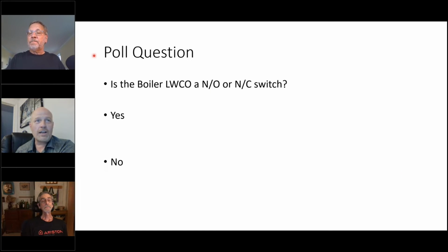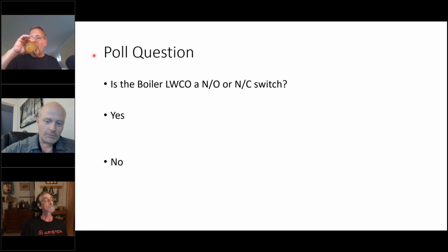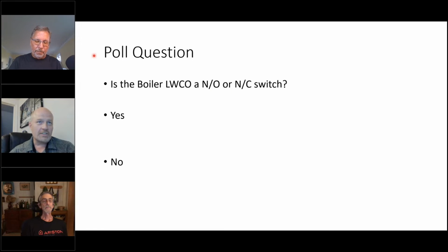So although the low water cutoff should remain closed anytime the boiler's operating, it's actually a normally open switch. The standalone condition of this switch, if you just sit it on your desk, when there's no water touching it, is in the open condition. It does not make the contact, and it's adding water that creates the contact. So although the switch itself generally remains closed for the life of the boiler, the switch's natural standalone position is actually open. So it's a normally open switch that closes upon the addition of water.